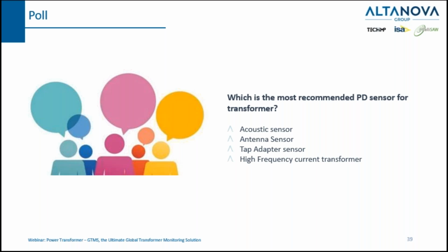If you also have a PD sensor already installed on the transformer, for example a UHF sensor on the oil valve, this kind of sensor can be connected without problems to the portable unit if you are interested in performing only a PD test, or to the GTMS if you want to integrate this kind of sensor in the global monitoring system.